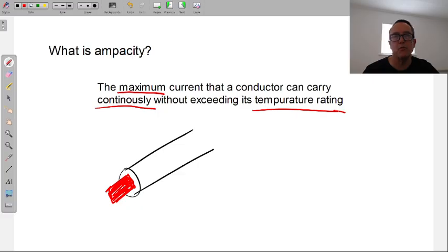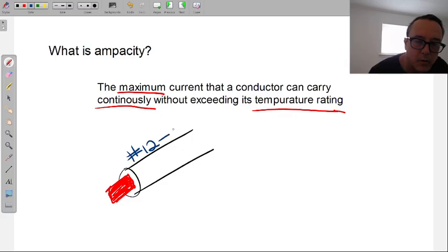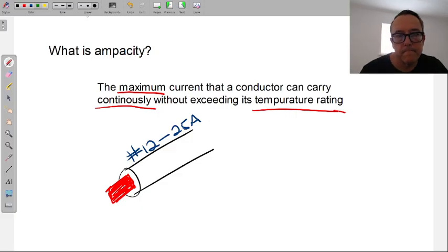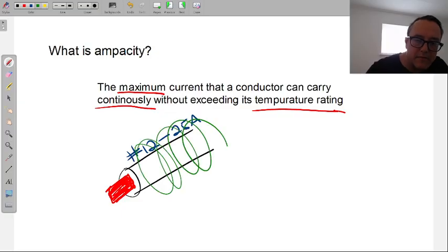So when it comes to over amperage on a circuit, it's really a little bit more than what the wire is rated for, hanging out there, that becomes a problem. It's not that a massive amount of amperage is going to break the wire. Let's say a number 12 is rated for 25 amps in the 90-degree column. If I were to put 27 amps on this, only a little bit more than the wire is rated for, I get a magnetic field from the amperage around the conductor. The real worry is the insulation.